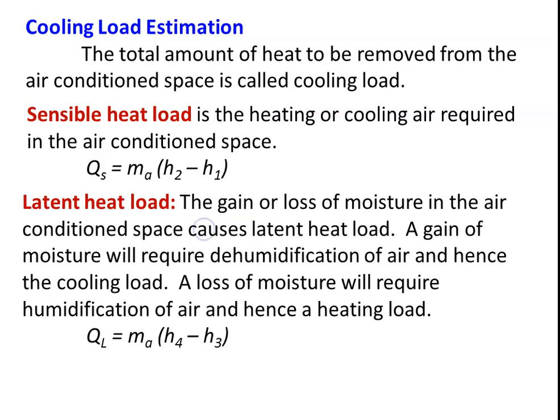Latent heat load: the gain or loss of moisture in the air conditioned space causes the latent heat load. When you add water vapor or remove water vapor, that changes the latent heat. A gain of moisture will require dehumidification of air and hence cooling load. A loss of moisture will require humidification of air and hence heating load. So when you heat, we have to add water vapor, that is humidification. So heating and humidification go together. When you cool, we have to remove the water vapor, that is dehumidification. So cooling and dehumidification go together.